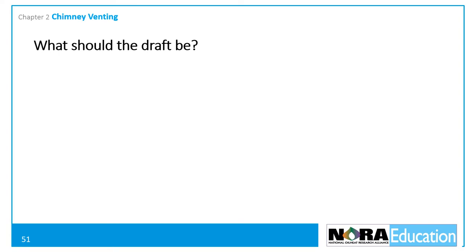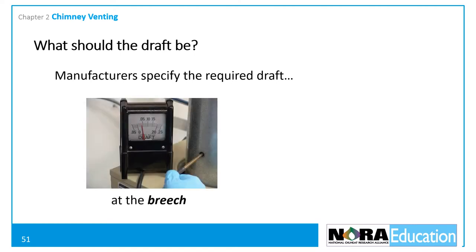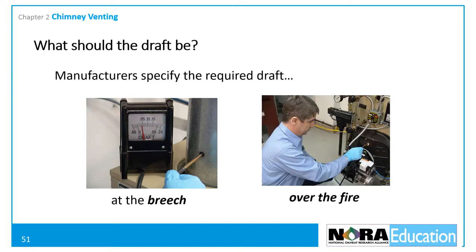How much draft does an oil heat appliance need? The answer is, it varies. Oil heat equipment manufacturers specify the amount of draft required in two places. The first is at the breach, which is in a straight piece of flue pipe on the appliance side of, and at least six inches from, the draft regulator. The second is over the fire, in the flame observation door just above the combustion chamber. Over-fire draft is normally about negative 0.02 inches of water column.